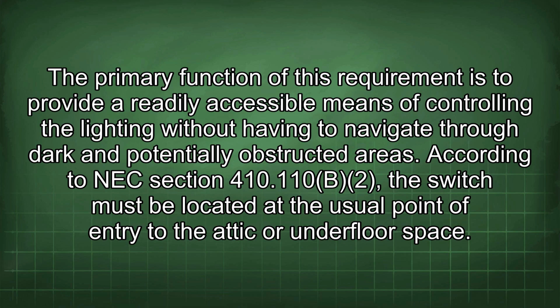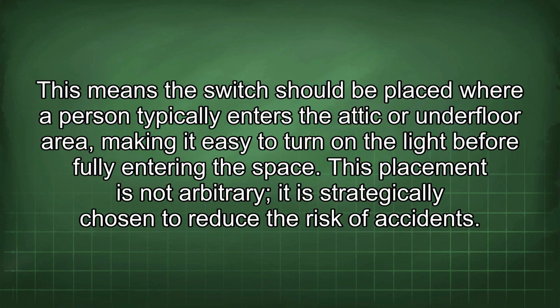According to NEC Section 410.110b2, the switch must be located at the usual point of entry to the attic or underfloor space. This means the switch should be placed where a person typically enters the attic or underfloor area, making it easy to turn on the light before fully entering the space.